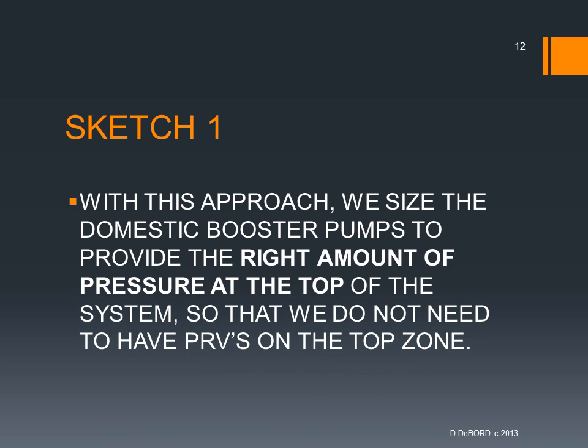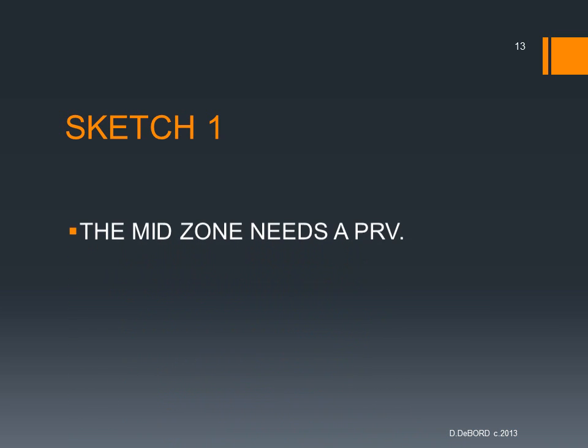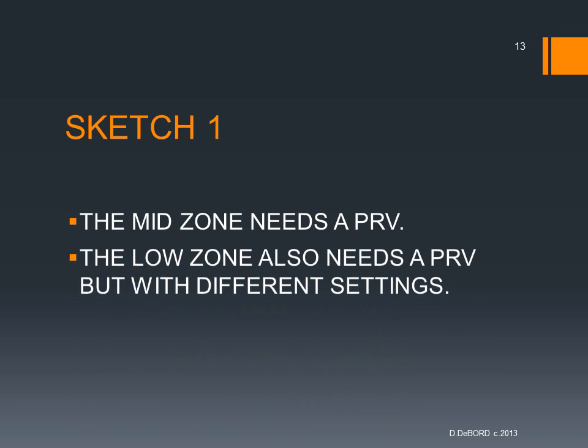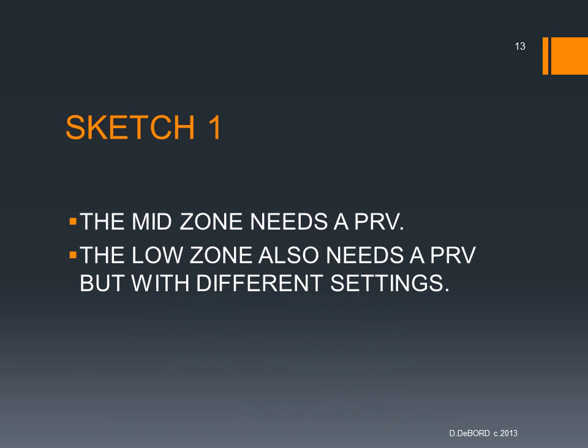So with this approach, we sized the domestic booster pumps to provide just the right amount of pressure at the top. And we do not need to have PRVs at the top zone because we designed the system for just the right amount of pressure at the top. This is not just for sketch 1, but this is always, but that is why we don't need the PRV at the top. The mid zone needs a PRV because we're picking up pressure from the static as it goes down, and the low zone also needs a PRV but with different settings.